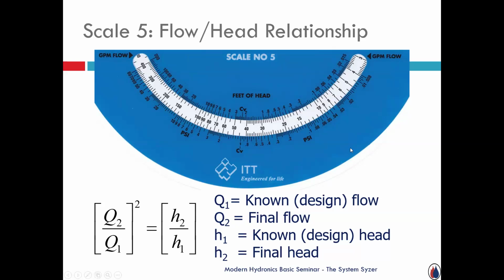But what we're saying is, when he built that scale for himself, when he's lining up these various numbers, it's based on this little formula here. As I change the flow, that change, whatever that answer is, square it times your original pressure drop, and that becomes your new pressure drop. I'll highlight it, and we'll touch on it a little bit in a couple of minutes. But you'll see the letters C sub V, or valve coefficient. We'll talk about that because that ties in with the valve industry, valve manufacturers, and their known pressure drops and how we can take advantage of that.